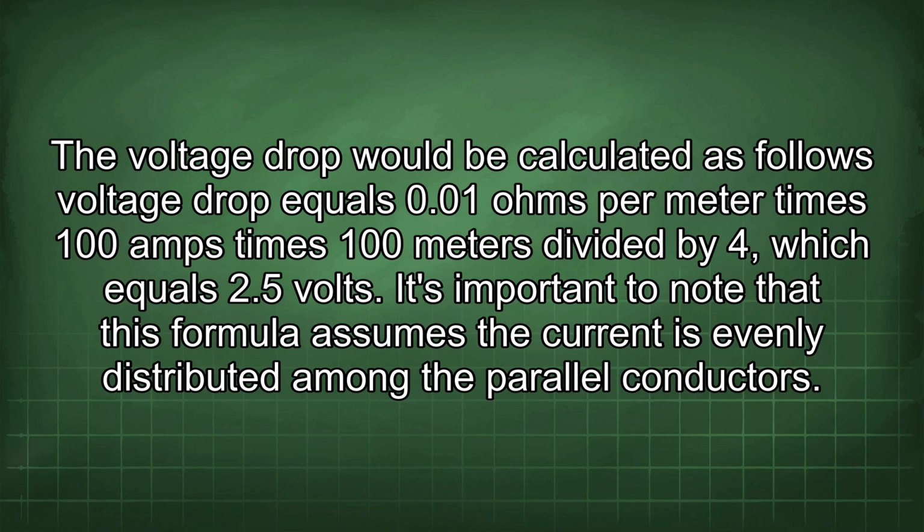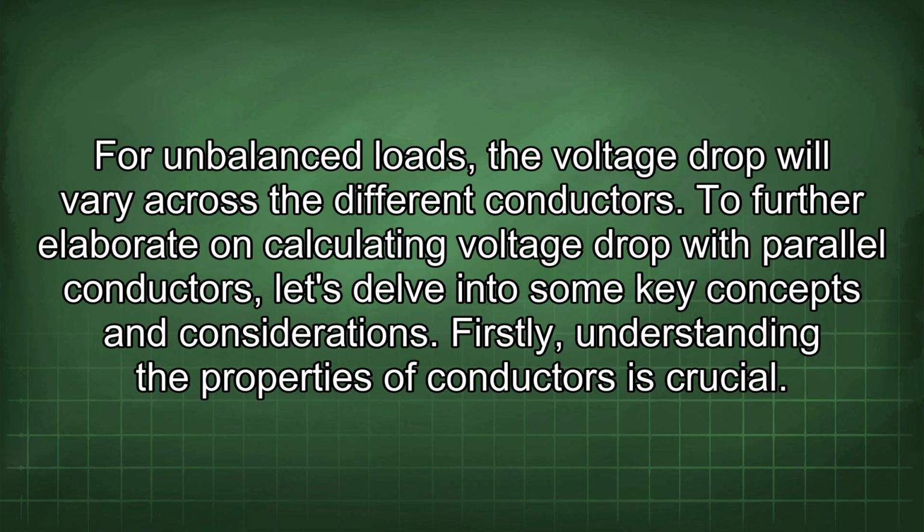It's important to note that this formula assumes the current is evenly distributed among the parallel conductors. For unbalanced loads, the voltage drop will vary across the different conductors. To further elaborate on calculating voltage drop with parallel conductors, let's delve into some key concepts and considerations.